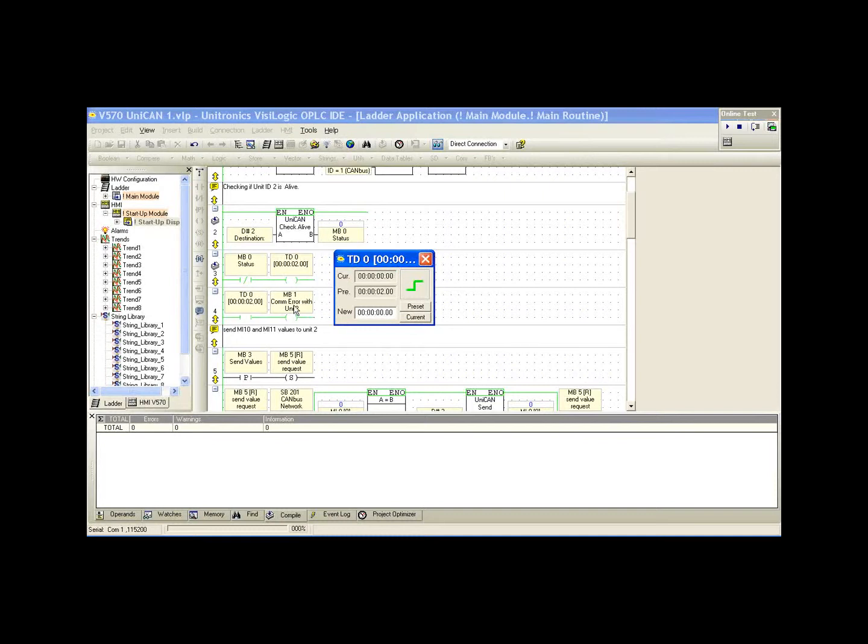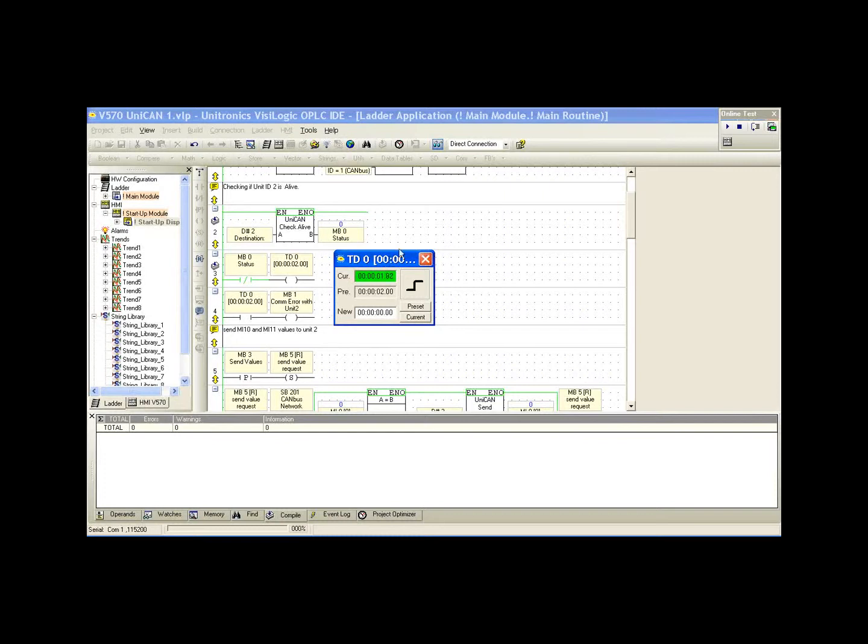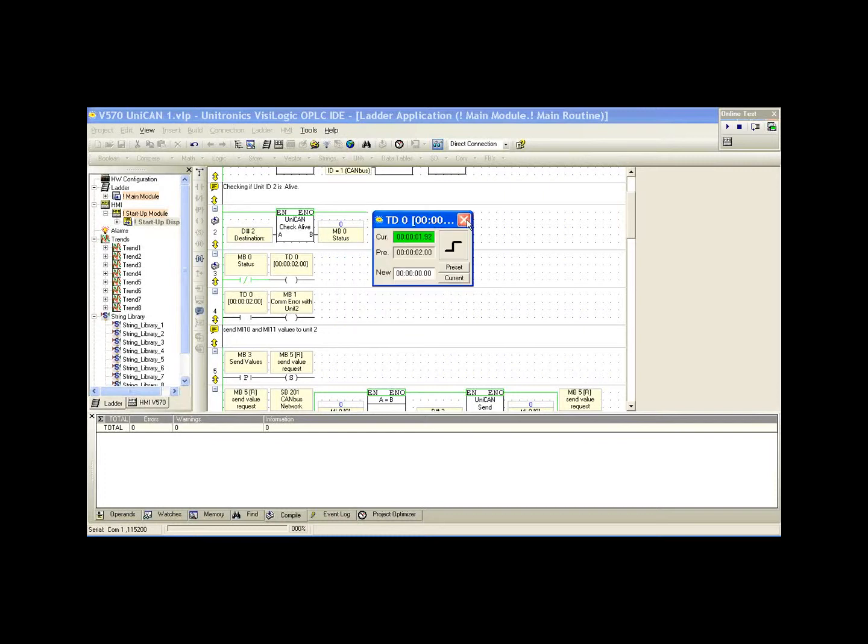Now below, we activate MB1, which is our status message on the HMI. We're now displaying COM error with unit 2 on the HMI. If I plug the cable back up, since it's a TD-type timer, we reset the timer, MB1 goes low again, and we can continue communication. This is simply the check-alive function block.